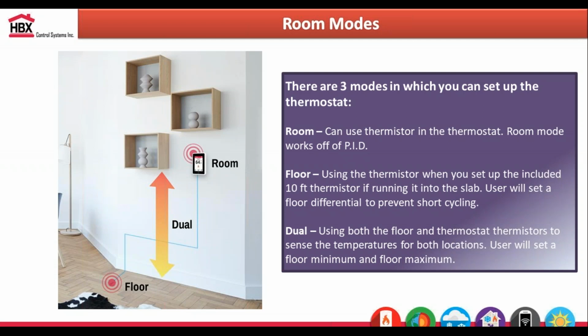Again, we give you that external sensor, so it's up to you to use it or not. If you want, you can use that sensor to go off the floor, off outdoor temperature, or if you want a room average with the stat and the sensor. So you have about 4 or 5 different options for how you want to use that external sensor with that HBX stat.